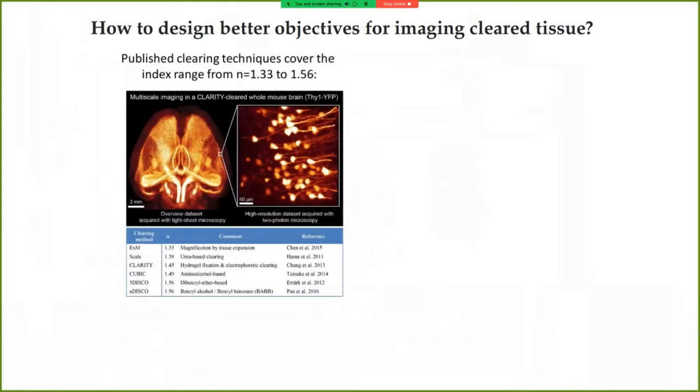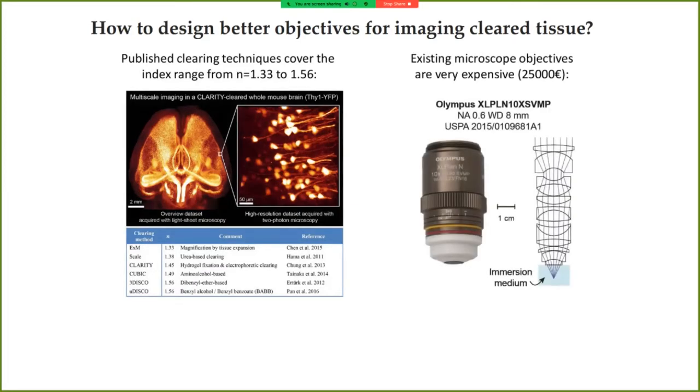So the challenge I'm addressing here is the question of how can we design better objectives for imaging cleared tissue? And imaging cleared tissue is a hard problem because currently we have such a wide range of different indices for immersion media that published clearing techniques cover. For example, for expansion microscopy, samples usually need to be imaged at an index of 1.33 or in water, whereas for organic solvent techniques, oftentimes we're imaging with indices of 1.56. And even though this is only part of what glass types cover, this is actually a pretty gigantic index range to properly correct microscope objectives for. And as a result, existing microscope objectives to cover at least part of this range are very expensive.